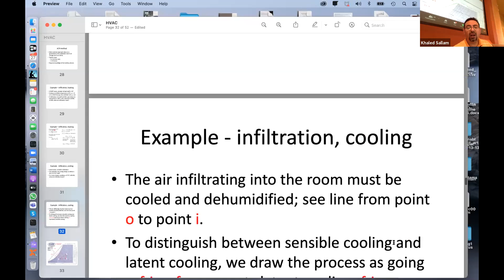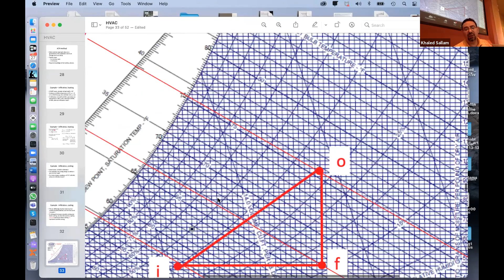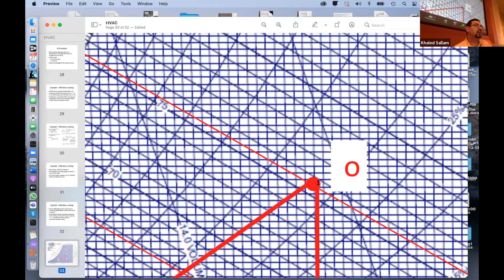Now, if you figure out what is the M dot, how did you get the M dot? Volume of the house multiplied by how many air changes per hour, is it 2.5? And you divide over the specific volume, right? And specific volume you can get also from the psychrometric chart, from those vertical lines, you see the volume, cubic feet per. So if it's here, that air would be the one that will leak in, so you'll be able to calculate the specific volume. So all those will allow you to calculate the M dot, multiply by delta H, and you get yourself the answer.